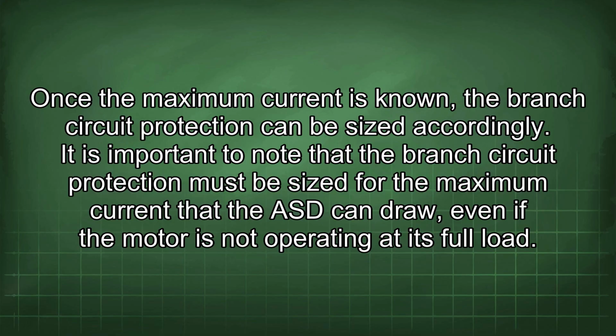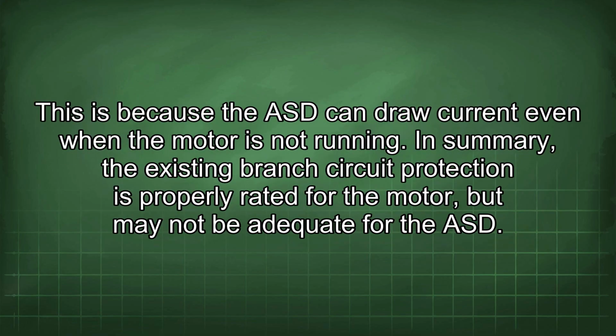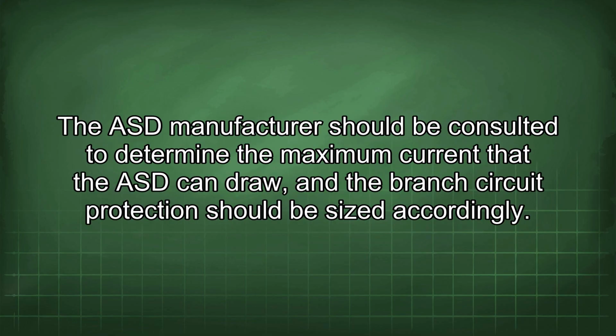It is important to note that the branch circuit protection must be sized for the maximum current that the ASD can draw, even if the motor is not operating at its full load. This is because the ASD can draw current even when the motor is not running. In summary, the existing branch circuit protection is properly rated for the motor, but may not be adequate for the ASD. The ASD manufacturer should be consulted to determine the maximum current that the ASD can draw, and the branch circuit protection should be sized accordingly.